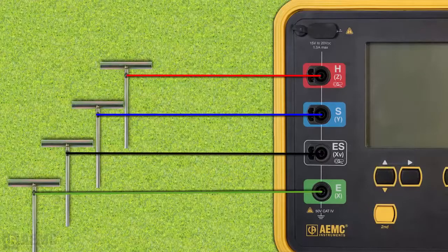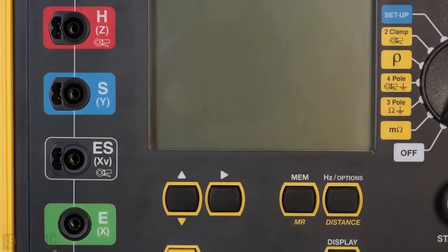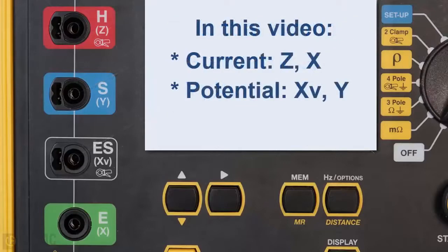According to international standards, the current terminals are called H and E. Some manufacturers label these terminals Z and X, while others use C1 and C2. Similarly, international standards define the potential terminals as S and ES; on some instruments these are labeled Y and XV, and on others P1 and P2. In this video, we will refer to the current terminals as Z and X, and the potential terminals as Xv and Y.